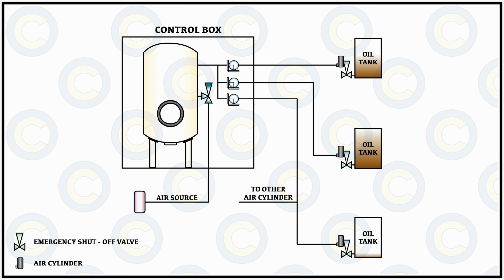So now let us imagine that at one branch, I go and change the position of the lever and thus open the valve, and this air goes and triggers the particular branch of the QCV that we are talking about. So let's say an amalgamation of 4 or 5 valves and shuts them at once. In normal testing in the engine room, what we do is that we keep designated people at the locations where the most critical valves are present.